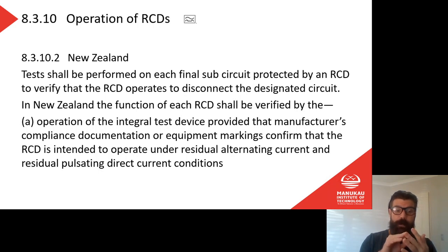But for now, what we need to understand is that we use a special meter to do that, an RCD tester. We plug it in, we select the right function, push the button, and it's going to tell us a specific piece of information. It's how long it's taken to trip, or how many milliamps it took to trip it, or something like that. And then we'll learn later what the requirements are: how fast it should be tripping, how much current, all of that kind of stuff.